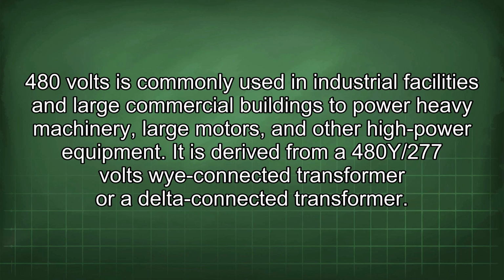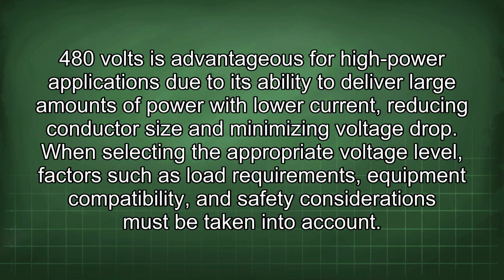480 volts is commonly used in industrial facilities and large commercial buildings to power heavy machinery, large motors, and other high-power equipment. It is derived from a 480Y/277 volts Y-connected transformer or a delta-connected transformer. 480 volts is advantageous for high-power applications due to its ability to deliver large amounts of power with low current, reducing conductor size and minimizing voltage drop.